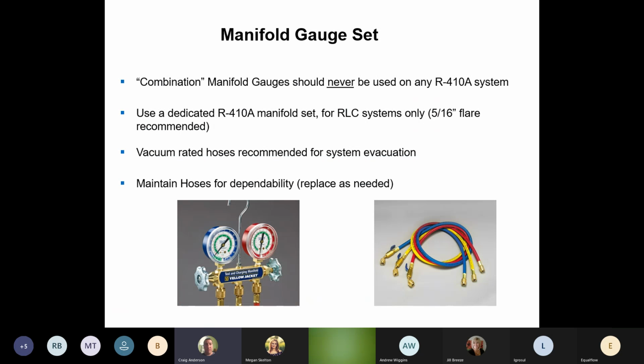So, my gauge sets, let's not mix and match them. If you're working with R22 and you're working with 410A, have two sets of gauges. The oils don't mix properly, and the different refrigerants actually eat away at each other. So keep your gauges away from mixing Freon.